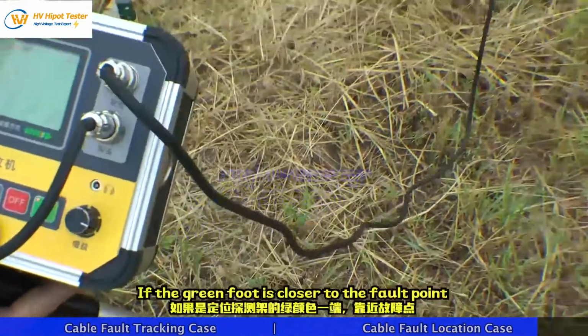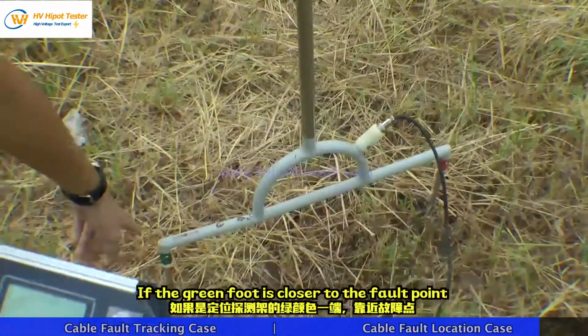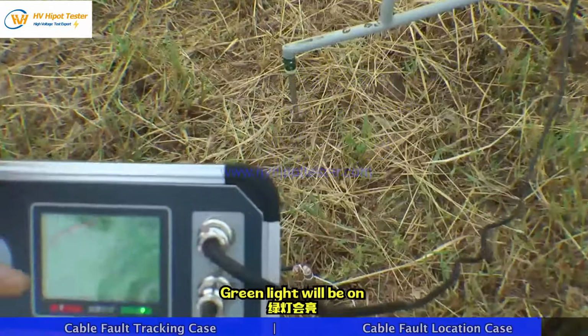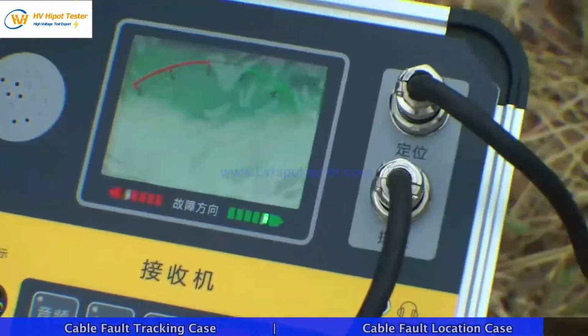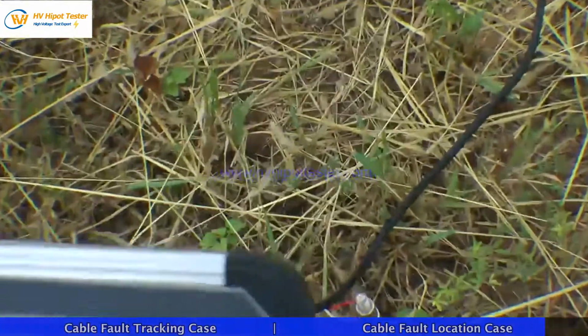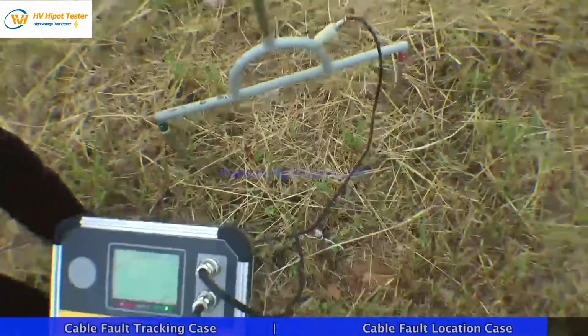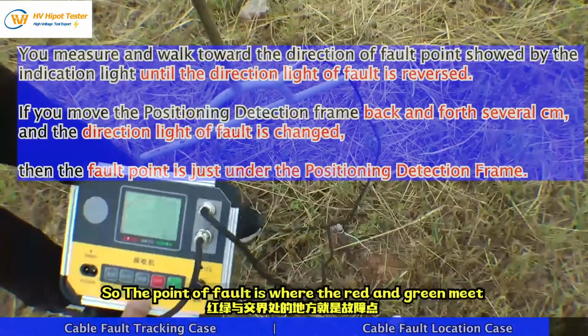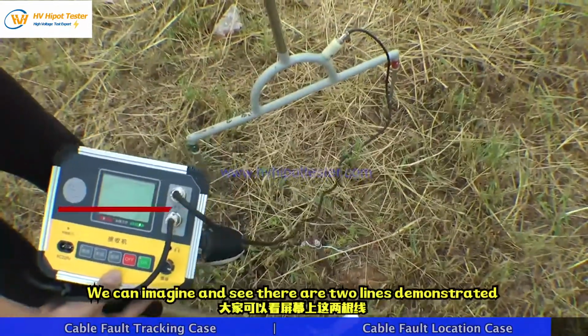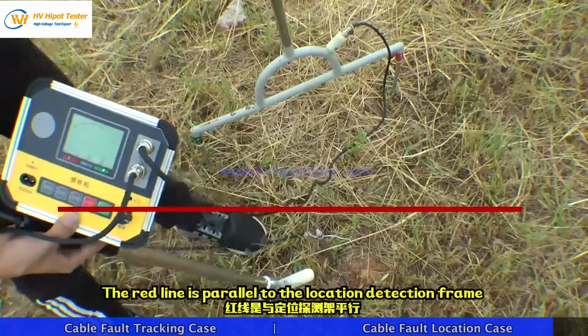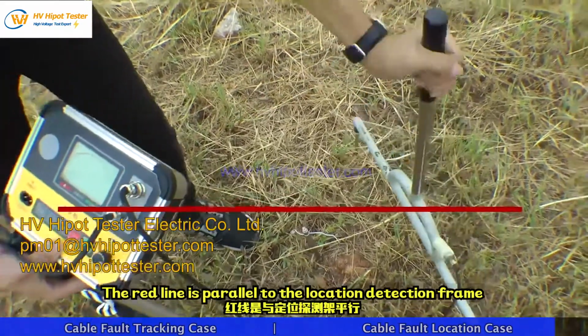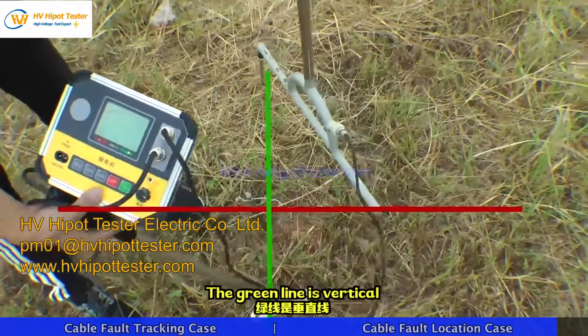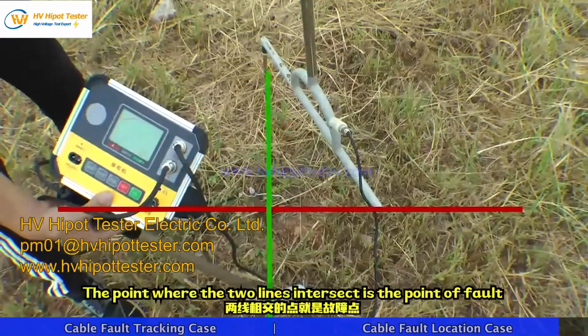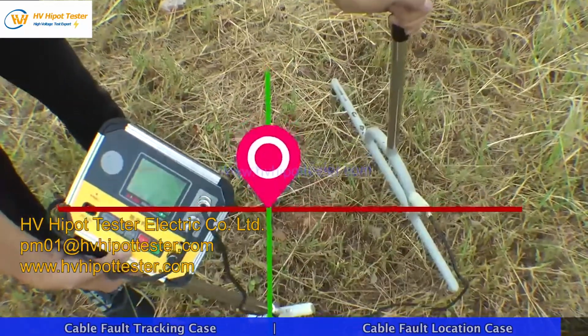If the green foot is closer to the fault point, the green light will be on. So the point of fault is where the red and green meet. We can imagine and see there are two lines demonstrated. The red line is parallel to the location detection frame. The green line is vertical. The point where the two lines intersect is the point of fault.